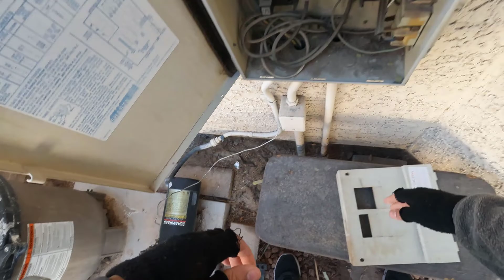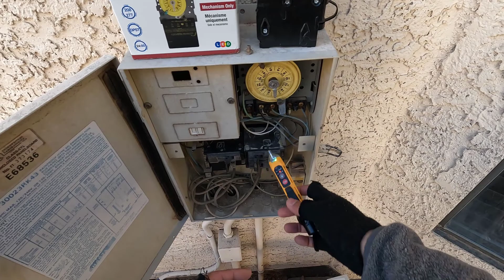When you don't lock your panels up properly, you run the risk of dust and debris flooding in there. You might lose a good connection with your circuit breakers or perhaps even your timer, and you also unnecessarily or prematurely wear your circuit breaker.